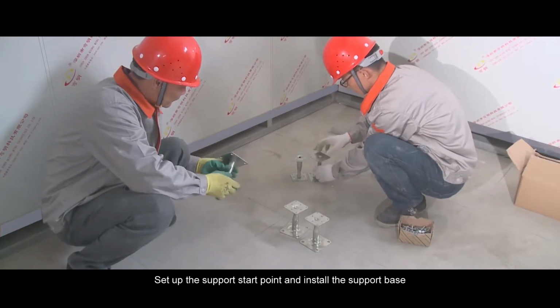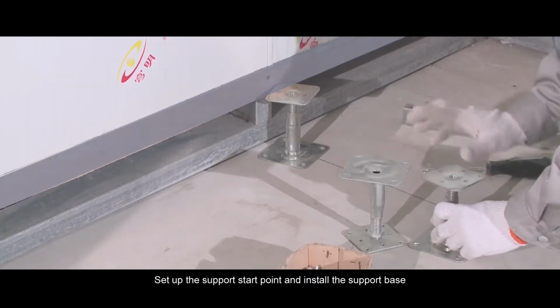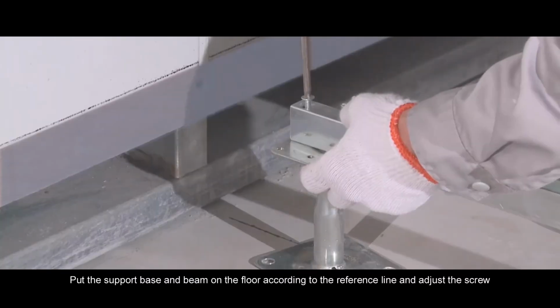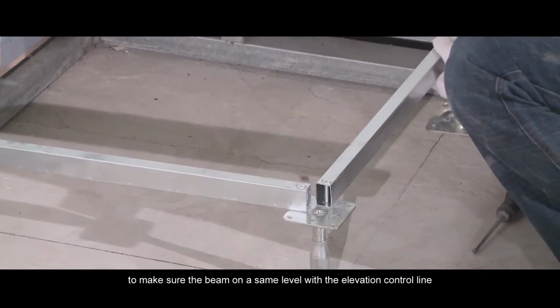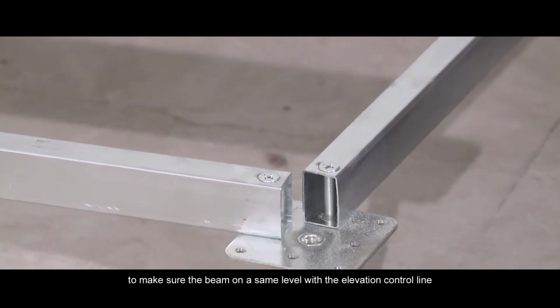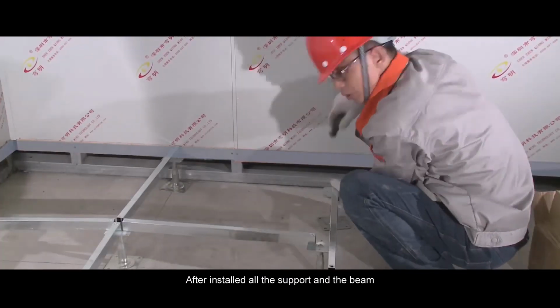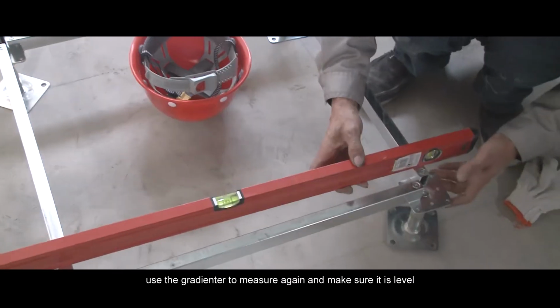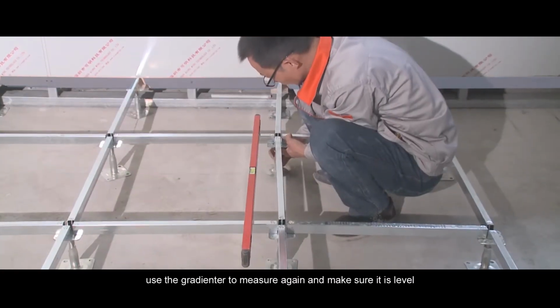Set up the support start point and install the support base. Put the support base and beam on the floor according to the reference line and adjust the screw to make sure the beam on the same level with the elevation control line. After installed all the support and the beam, use the gradienter to measure again and make sure it is level.